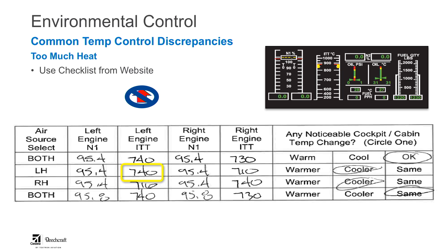So the real thing I'm looking at here is why didn't it go up when I selected left-hand source from when it was already in both? We determined that the flow control valve on the left side was actually stuck in the high position. Because it was stuck in high, it was adding 8 pounds per minute from the left side to 4 pounds per minute on the right side for a total of 12 pounds per minute of flow. That's too much bleed air coming into the system. The pressurization side can handle it, it can compensate, but all that hot bleed air couldn't be compensated by the temp control system, and that's why he was complaining about a hot cabin.